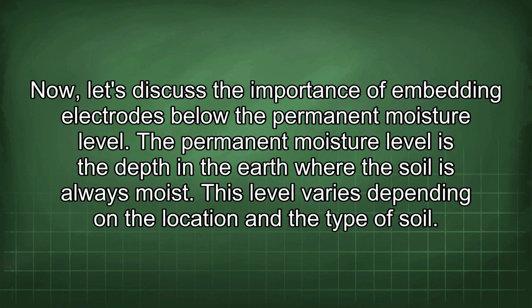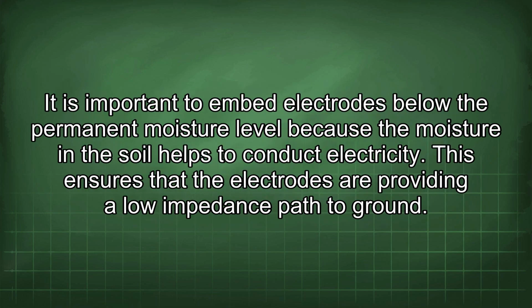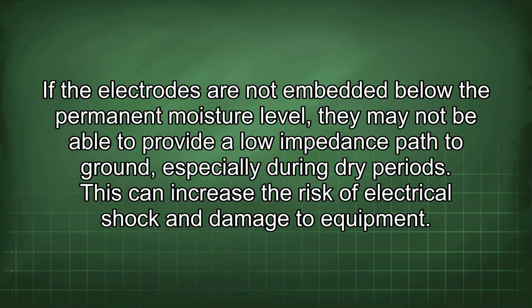Now let's discuss the importance of embedding electrodes below the permanent moisture level. The permanent moisture level is the depth in the earth where the soil is always moist. This level varies depending on the location and the type of soil. It is important to embed electrodes below the permanent moisture level because the moisture in the soil helps to conduct electricity. This ensures that the electrodes are providing a low impedance path to ground. If the electrodes are not embedded below the permanent moisture level, they may not be able to provide a low impedance path to ground, especially during dry periods. This can increase the risk of electrical shock and damage to equipment.